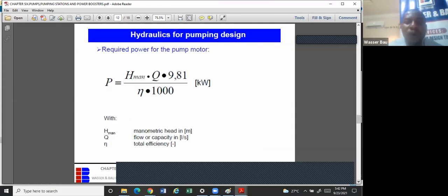Okay, good. So we've also discussed this. If you want to understand the hydraulics of a pumping, it's simply a function of the head and the discharge. The other things you see there are all constants. This 1,000 is to convert watts to kilowatts. This N here is the efficiency. This Q here is the flow. And this is acceleration due to gravity. So once you have the flow of a stream or a river, and you're asked to know the hydropower potential, it is easy. Once you know the discharge of a tank, you can say when that tank will discharge.